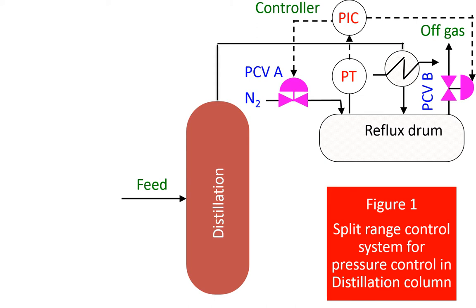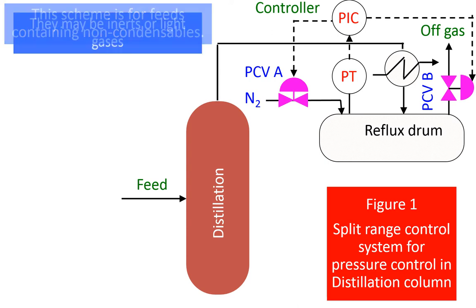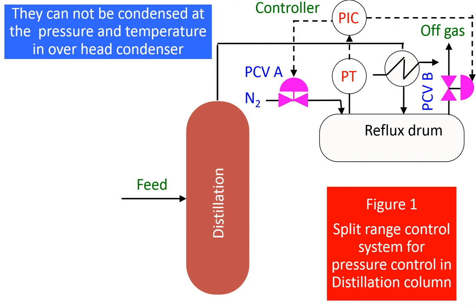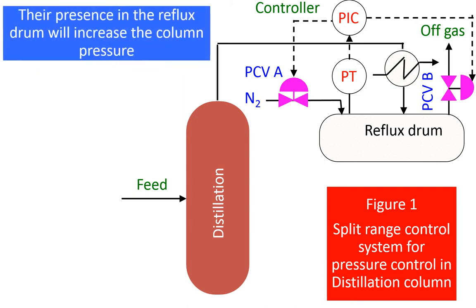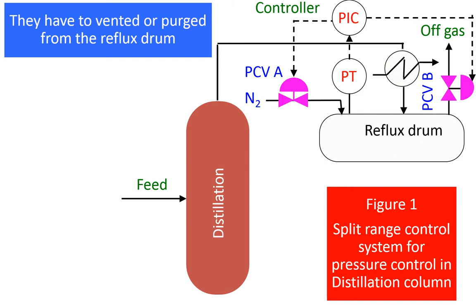The working principle of a split range control scheme in a distillation column is illustrated in this figure. In many instances, the feed to a distillation column consists of light gases which are essentially non-condensables at the operating pressure and temperature of the column. Hence, they accumulate in the reflux drum. Usually, in a distillation column without light gases, cooling water is used to control the pressure. In columns with feed containing inerts and non-condensables, the cooling water flow is not the desired method.